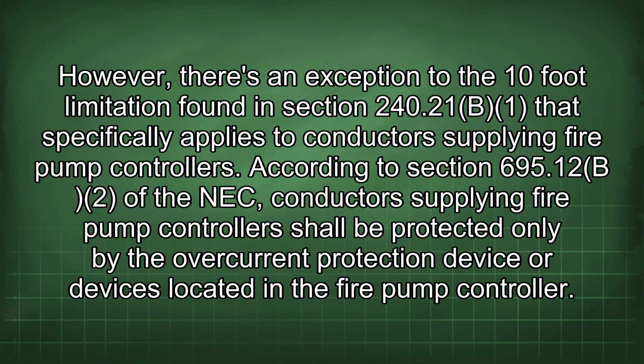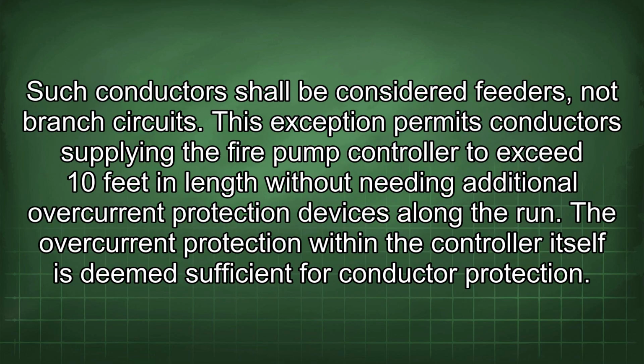According to Section 695.12(B)(2) of the NEC, conductors supplying fire pump controllers shall be protected only by the overcurrent protection device or devices located in the fire pump controller. Such conductors shall be considered feeders, not branch circuits. This exception permits conductors supplying the fire pump controller to exceed 10 feet in length without needing additional overcurrent protection devices along the run. The overcurrent protection within the controller itself is deemed sufficient for conductor protection.